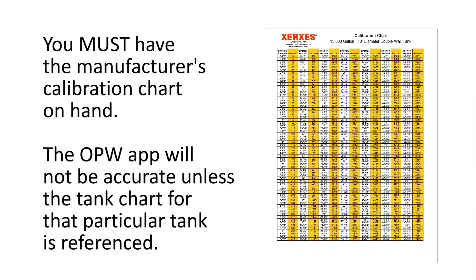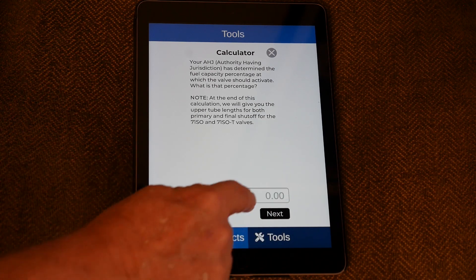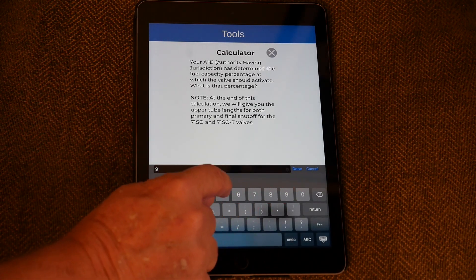The calculator will give you four values. You don't need to make any adjustments to your authority having jurisdiction percentage — just enter that percentage when it asks. Don't try to pre-calculate adjustments for final shutoff versus primary; we're going to give you those values. Just follow the directions the app gives you. You're going to need a tank chart — if you do not have a tank chart, you can't use this application. You can't guess at the numbers; you must have the actual tank chart for the tank you're installing this valve into.